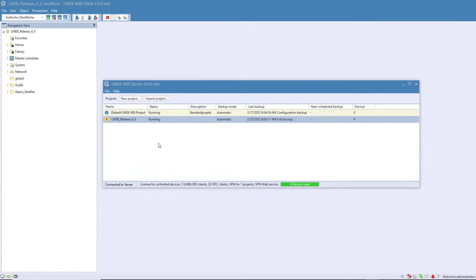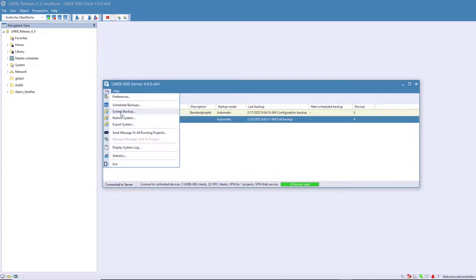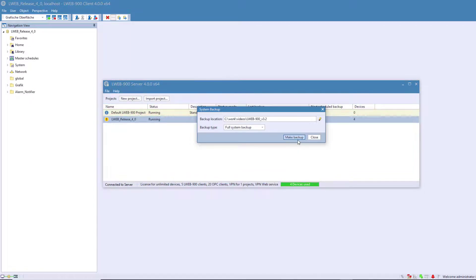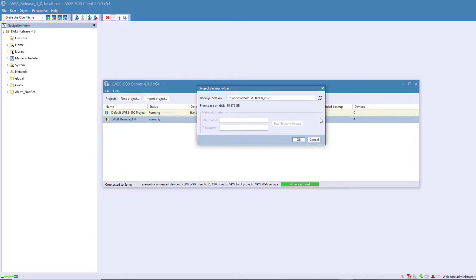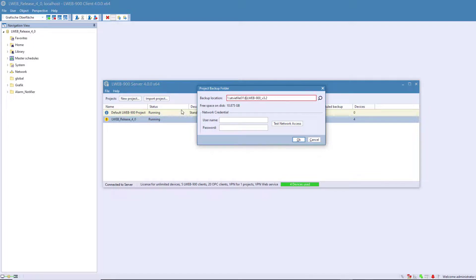Project Backups can now also be created on a network basis. To do this, select System Backup and change the location to a network drive. Caution, the so-called UNC path must be specified here since the network drives are not mapped when the LWeb 900 server is running.